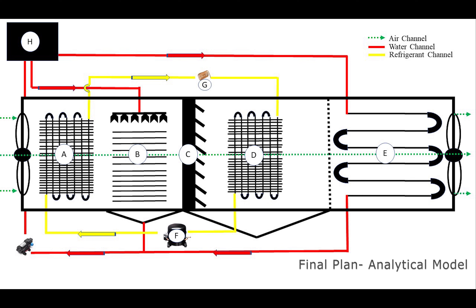After iterations, this was the final plan for the analytical model, wherein ambient air is taken in by induced draft fans and passed through the condensers for preheating of air, which increases its capacity to carry more water vapor. The hot water is then sprayed out in cross flow through plastic fills for the humidification process.